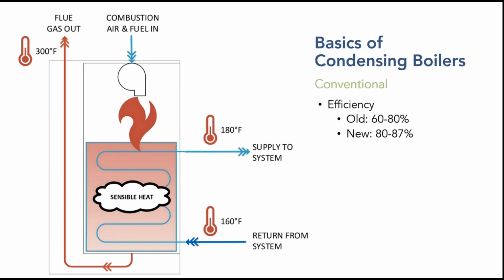So here's the concept. This is a conventional boiler for comparison. You have a burner taking air and fuel in, firing across a heat exchange surface, and those flue gases give up sensible heat to your hot water. Traditionally, hot water systems are designed to a set point of about 180 degrees with a 160-degree return. So this is all sensible heat. Your flue gas exits the boiler. Everything's still vapor, and 300-degree outlet temperature can vary, but that's a reasonable outlet temperature.